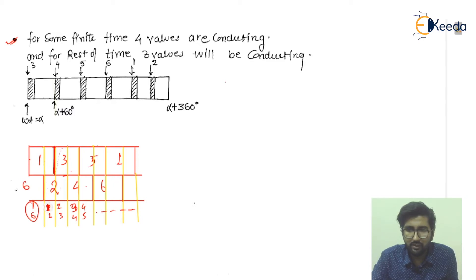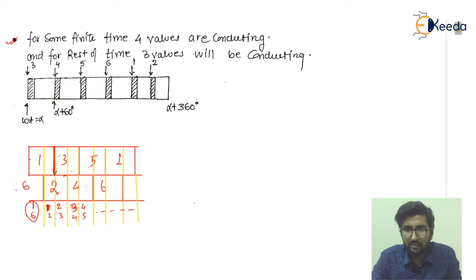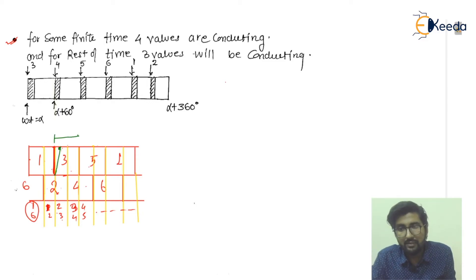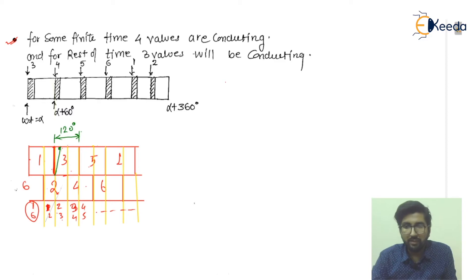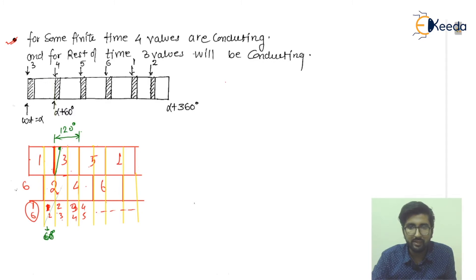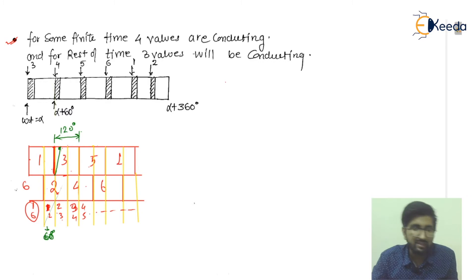Due to leakage inductance, valve one will operate for longer than the decided value of 120 degrees. Each thyristor is supposed to conduct for 120 degrees, meaning each interval is 60 degrees. With six thyristors operating across six intervals of 60 degrees each, the total is 360 degrees — that is the valid full-cycle operation.